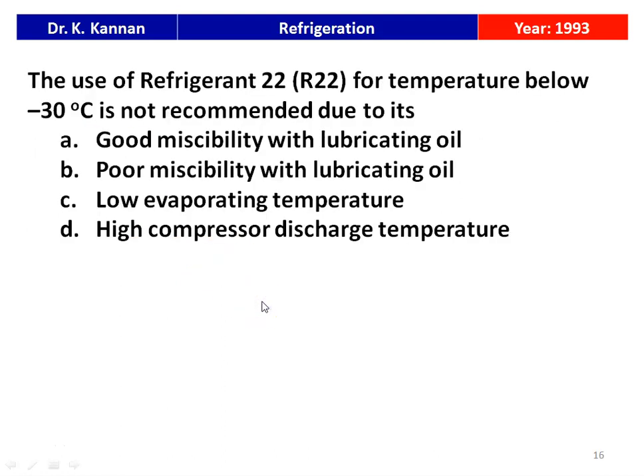The next question is from the 1993 question paper. Use of refrigerant R-22 for temperatures below minus 30 degrees Celsius is not recommended due to: good miscibility with lubricating oil, poor miscibility with lubricating oil, lower evaporating temperature, or higher compressor discharge temperature. The answer is higher compressor discharge temperature. Use of R-22 below −30°C is not recommended due to the higher compressor discharge temperature.